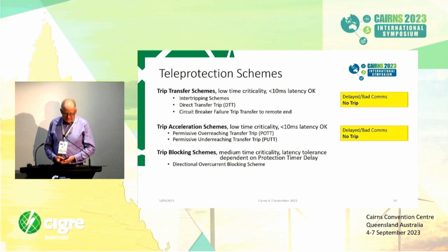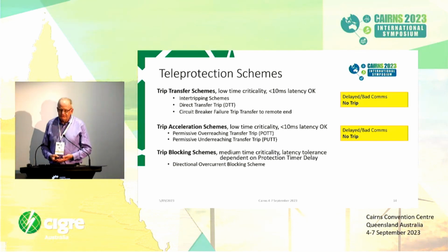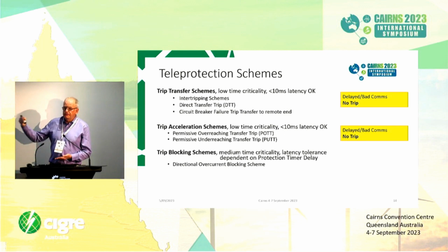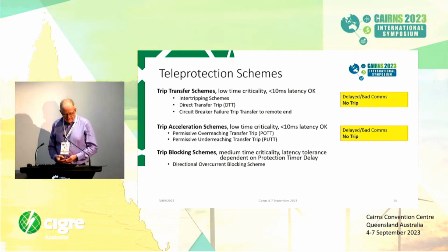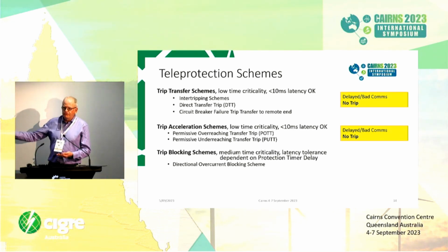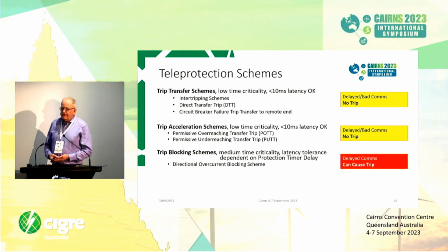So the next scheme is a trip blocking scheme. This has got medium time criticality. This involves sending a blocking signal from one station to another station to block the protection operation, so you don't get coincident tripping of non-faulted parts of your network. We just need to make sure that that blocking signal gets to the remote end in time to block, to not trip the other section of the network. The problem, though, is if that signal gets delayed or doesn't arrive at the other end, you're going to start tripping off the other part of your network.